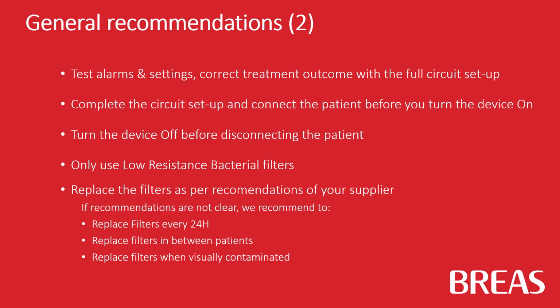Only use low-resistance bacterial filters. And replace the filters as per recommendations of your supplier. If the recommendations are not clear, we recommend to replace filters every 24 hours, replace filters in between patients, and replace filters when visually contaminated.